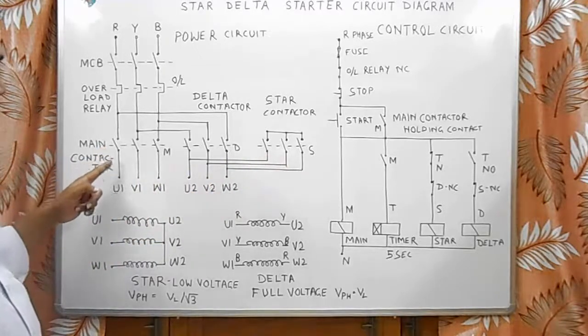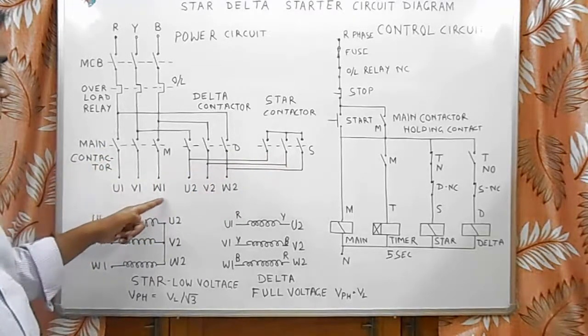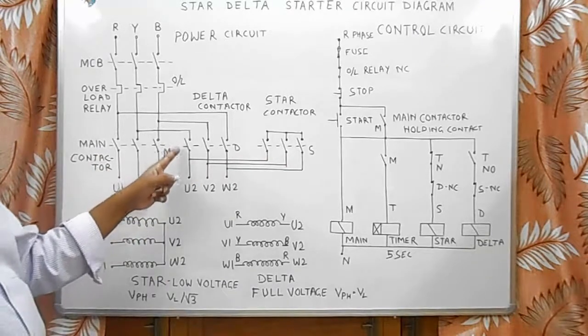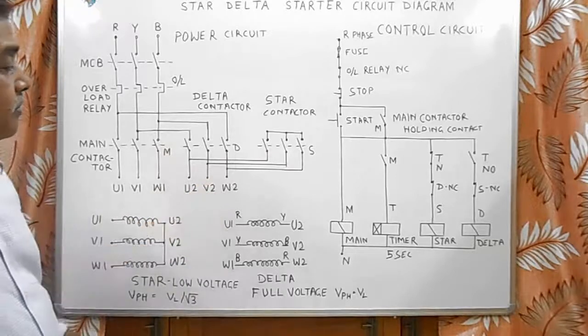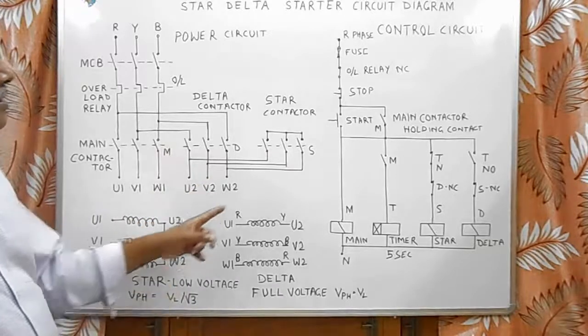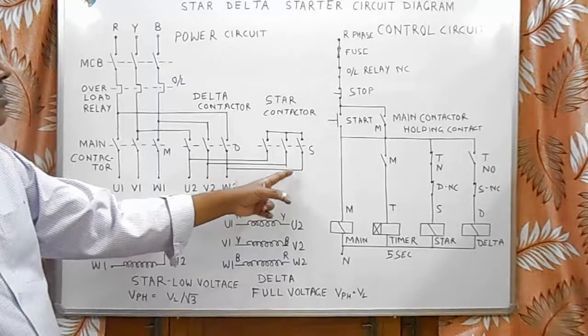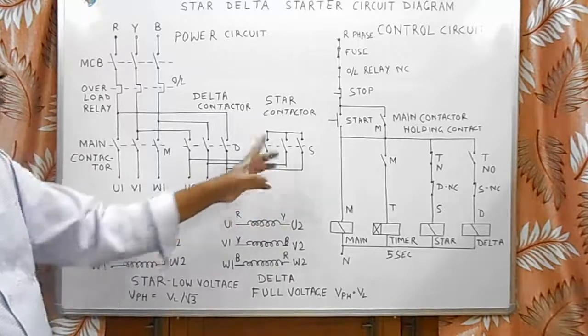The main contactor gives supply to U1, V1, and W1. Delta contactor gives supply to U2, V2, and W2. Whereas the star contactor is used to make short circuit of U2, V2, and W2.